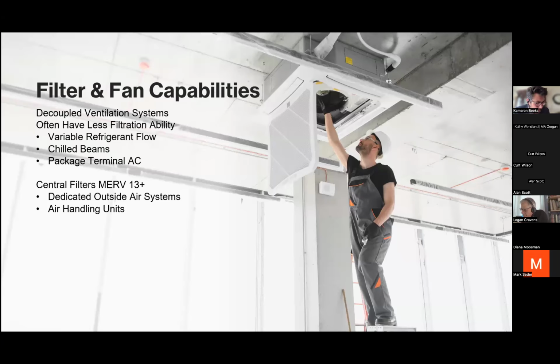Now, Oregon really celebrates decoupled ventilation systems. What that means is that I am using a separate outside air system from my in-zone cooling and heating systems. So a lot of people might see series fan power boxes, might see variable refrigerant flow, see chilled beams. Those are the types of systems that I see in Oregon because we're trying to reduce what's called reheat energy losses. It saves a lot of energy.